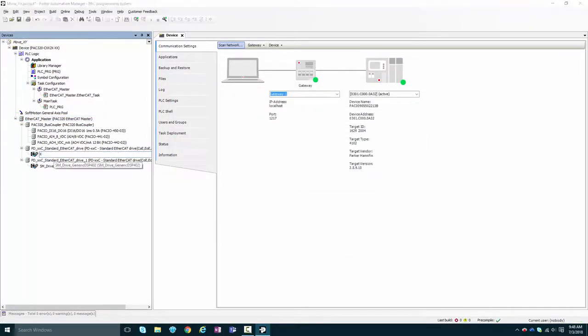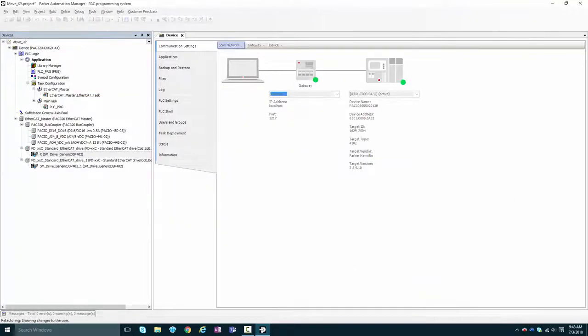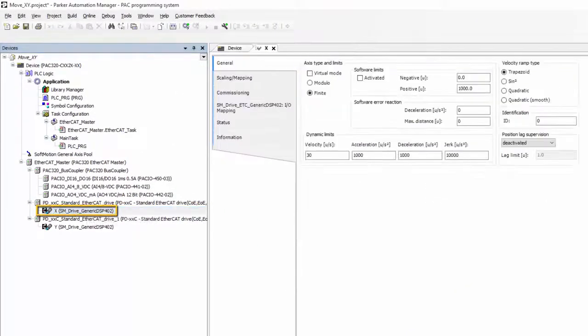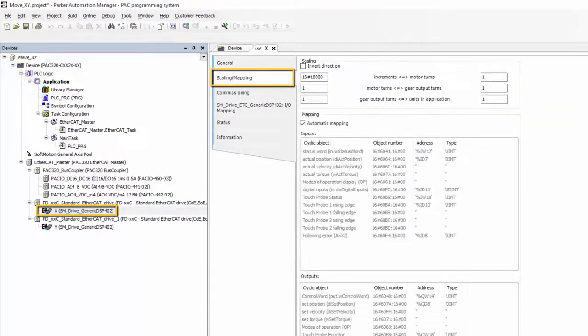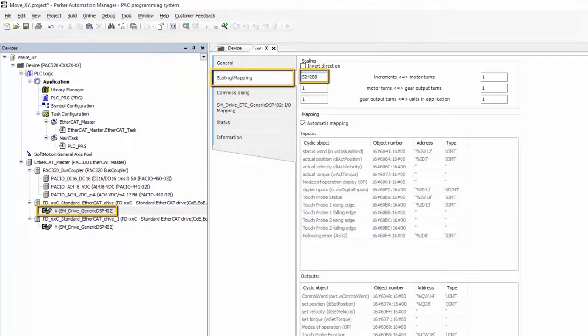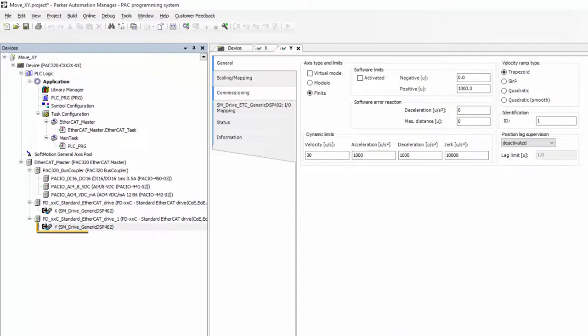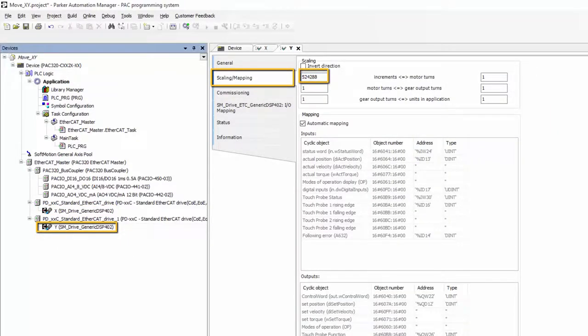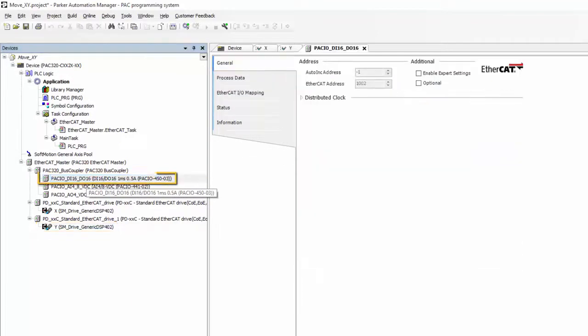Now I'm going to rename my drives X and Y, and since I know these P-series drives have a resolution of 524,288 counts per rotation or pulses per rotation, I'm going to scale them so that my user units are in revs.